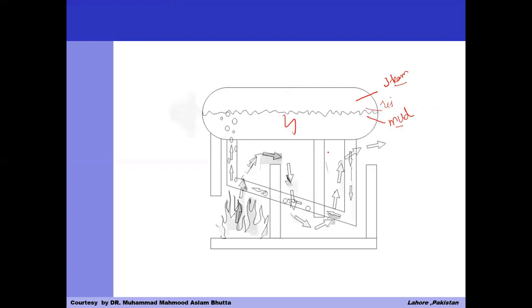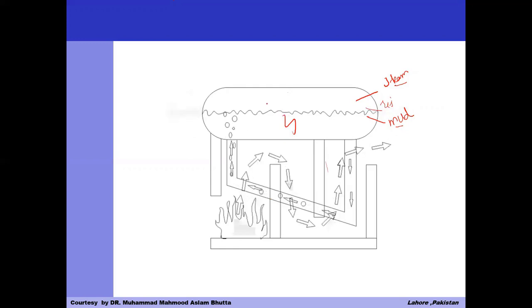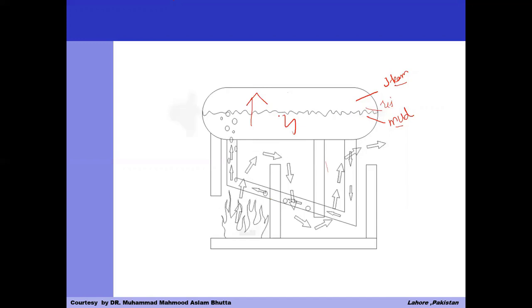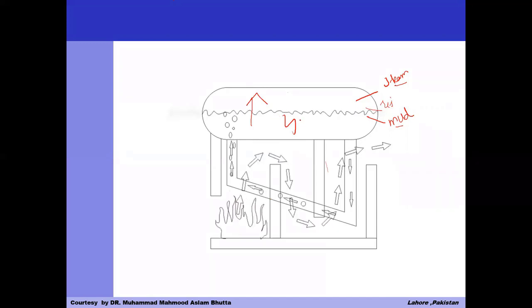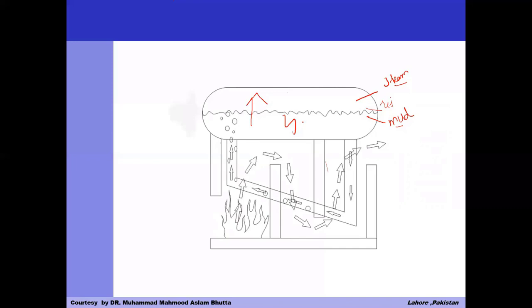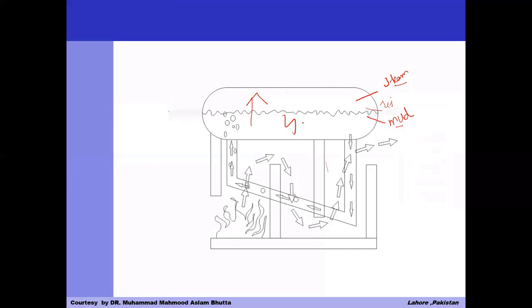The colder water pushes the hotter water upward through the riser, so there is a natural flow of water in the boiler system. As more and more steam is produced, the pressure of the system increases, which obstructs the natural flow of the water, and hence the rate of production of steam becomes low. Again, if the steam is taken through the steam outlet, the pressure inside the system falls, and consequently the flow of water becomes faster, which results in faster production of steam.